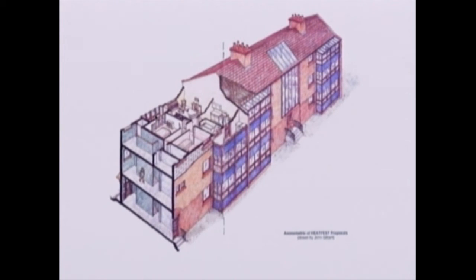Over and above insulation and the glazed spaces, which predominantly are helping in terms of, one could call it edge insulation, the other way to look at it is the ability to preheat air for ventilation. So the air coming into this bedroom, for example, is preheated in that space between the bedroom and the outside, and therefore cuts down on the ventilation loads. Similarly, air entering the kitchen, which will be fairly rapidly exhausted, instead of taking air at ambient temperature, is taking air at the temperature of the buffer space before it reaches the kitchen. And in the same way, air can be taken from the glazed veranda space via a French window into the living space rather than through the direct window.